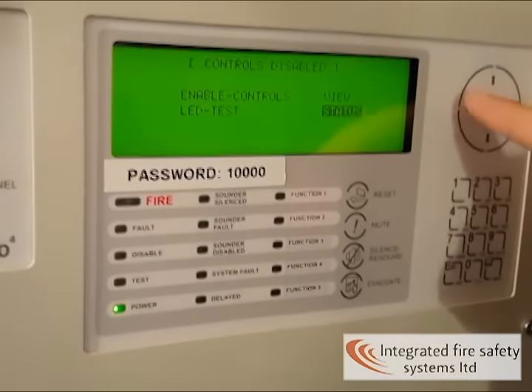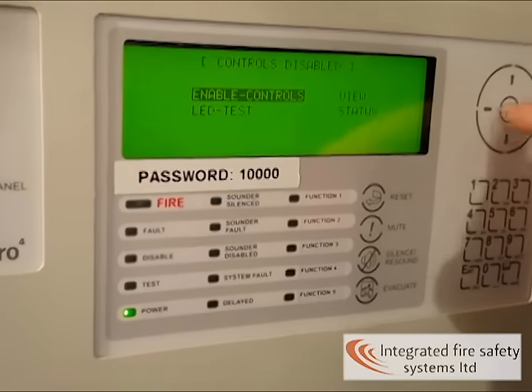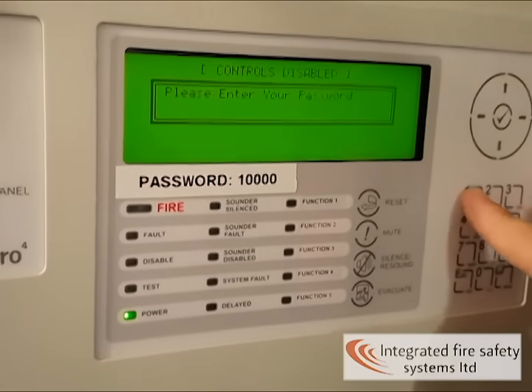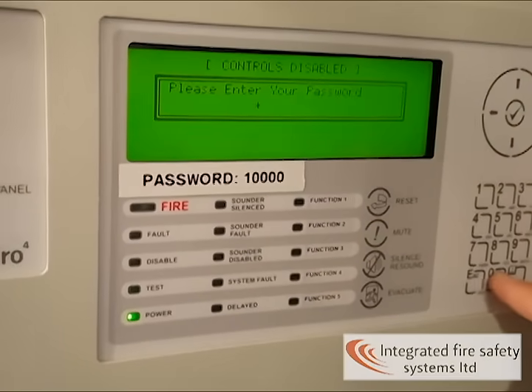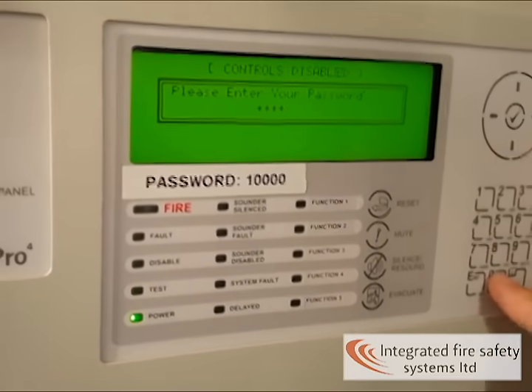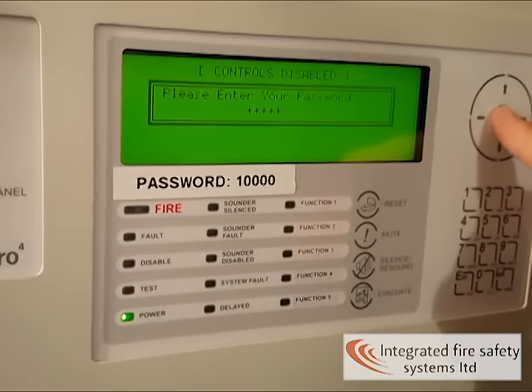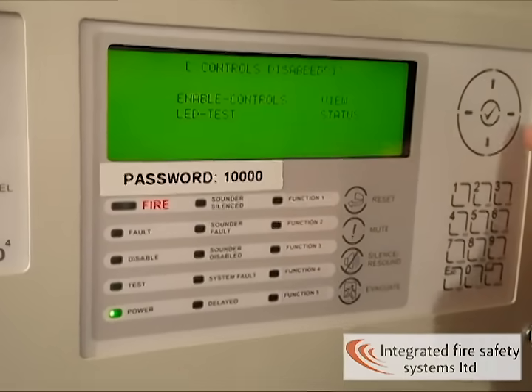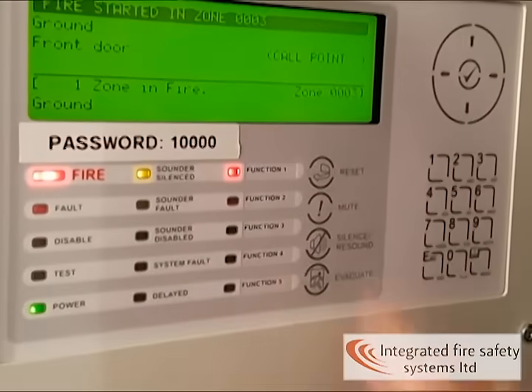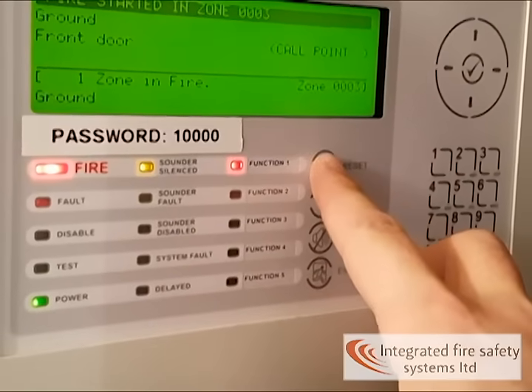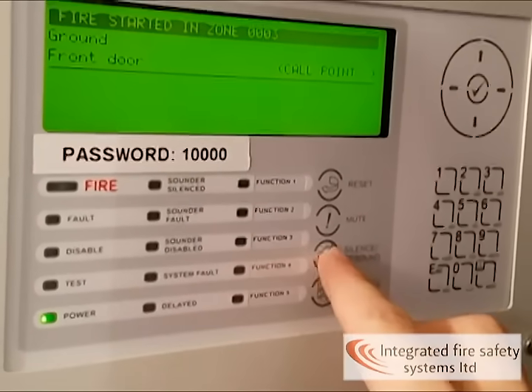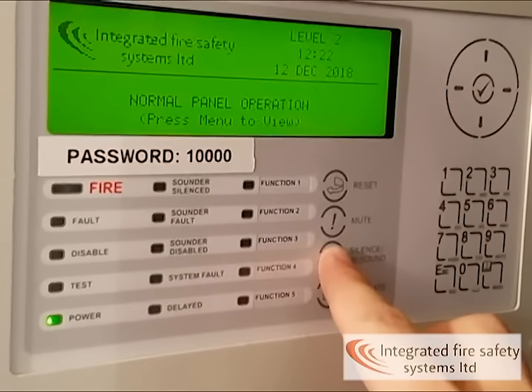To reset the fire alarm panel, first of all you have to access user level 2. Press any button and then select enable controls. Type in the password, which in our case is 10,000, and press the tick. Once you've accessed the user menus, you can press silence and reset. This will stop the alarms and reset the fire alarm panel.